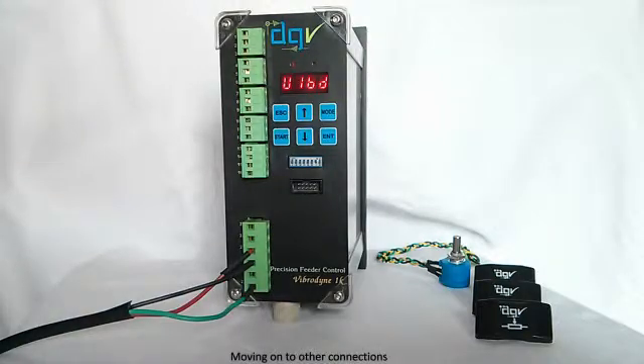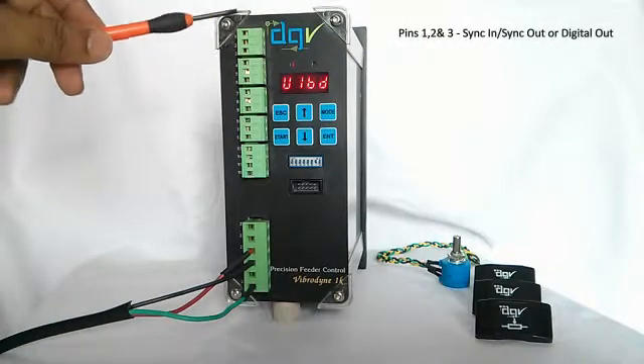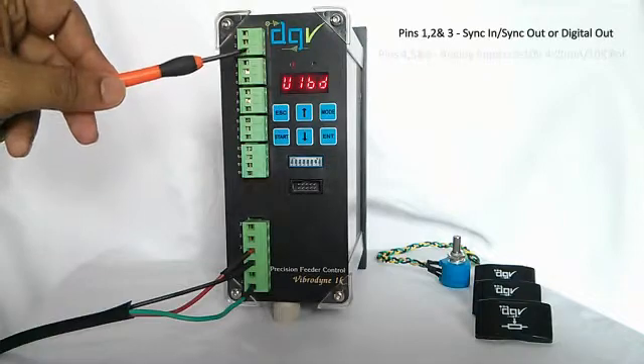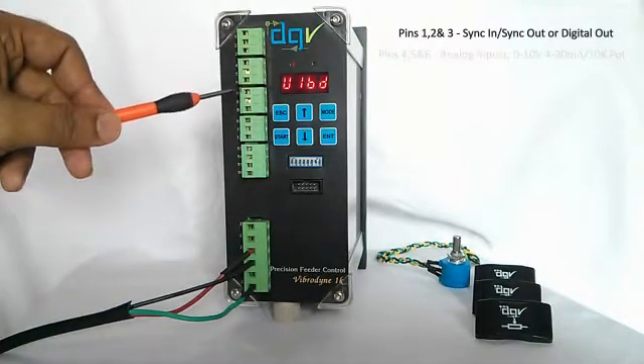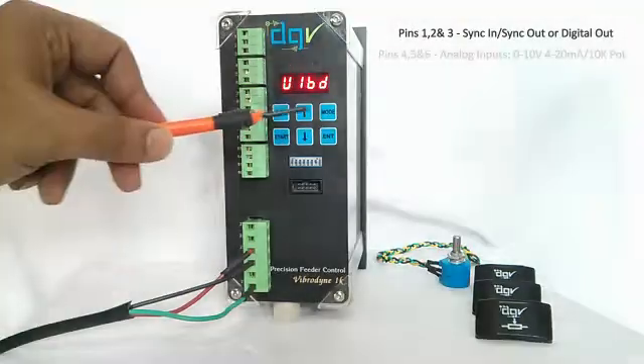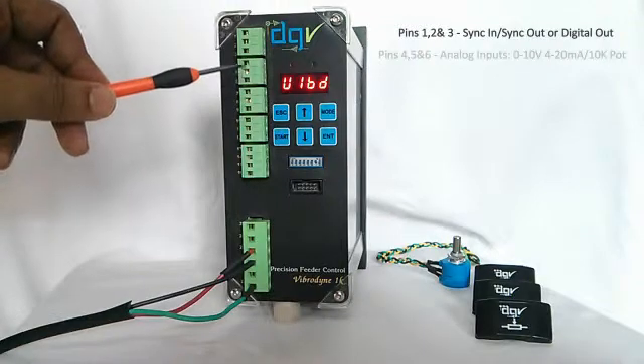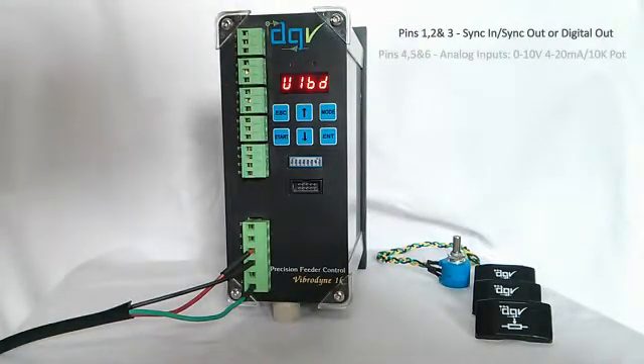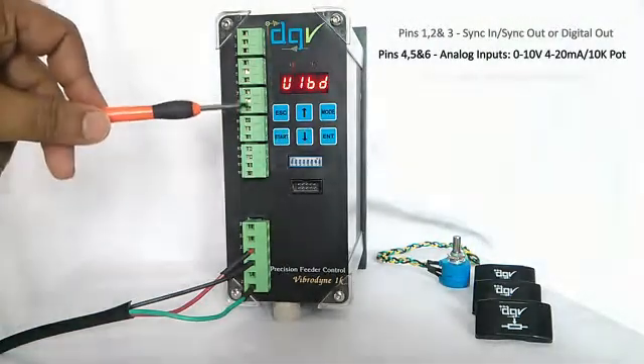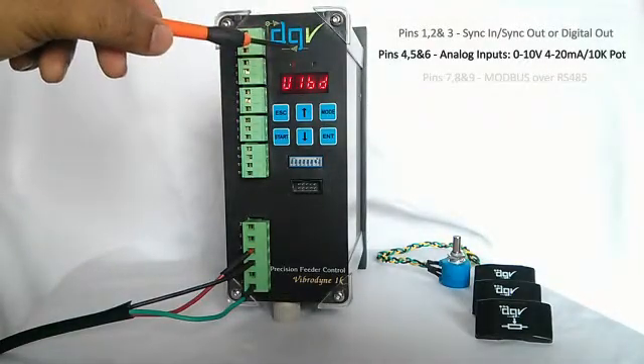Let us have a look at the other available interfaces and connections. The first three pins, or the first port, are for sync-in and sync-out connections — we will talk about that later. The next three are for your analog inputs. Instead of the keypad, if you want to control it with a potentiometer, a 4 to 20 mA signal, or a 0 to 10 volt signal, this is where you connect it.